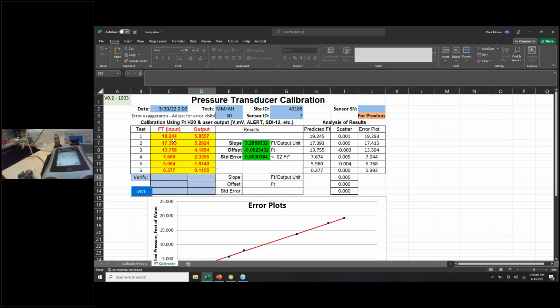So in this case, our slope was 3.28. So for every 1 unit that came out of the PT, we would actually need to multiply it by 3.2869332 to get it to feet. And the offset was minus 0.002. Now what's interesting is look at the standard error of this calibration. The specification says that the standard error is less than 0.1% of the full scale, which if this is a 20-foot PT, would mean 0.02 feet.